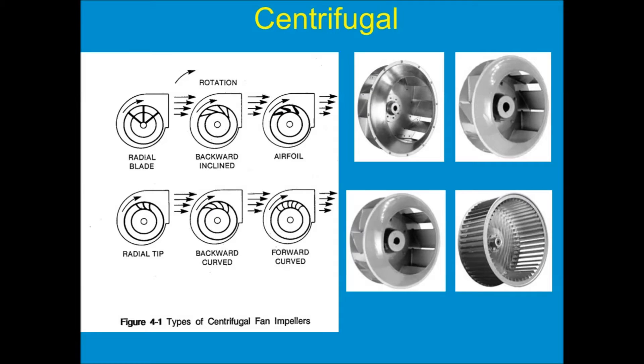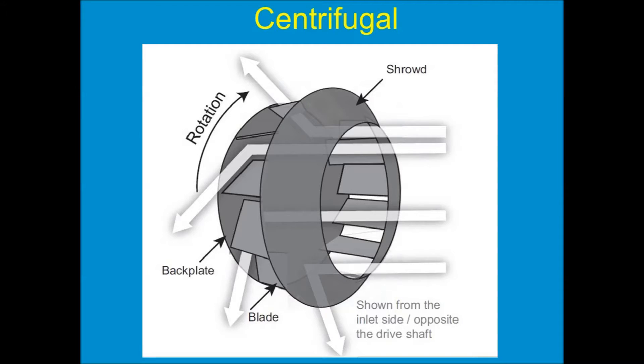Now unlike an axial impeller, as you can see here on these images of various types of centrifugal impellers, the impeller has a bunch of small blades attached to a ring. When the assembly rotates, these little blades push the air away from the center, creating a low pressure area in the center, so air is drawn in. Unlike an axial impeller where airflow is straight through, here the air is drawn in parallel to the axis of rotation, then turns 90 degrees and shoots off the wheel in a 360-degree pattern.